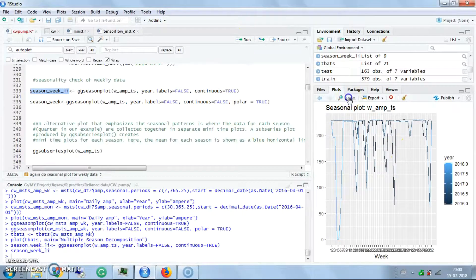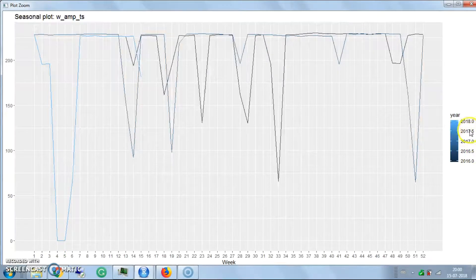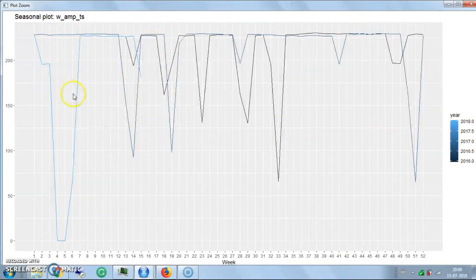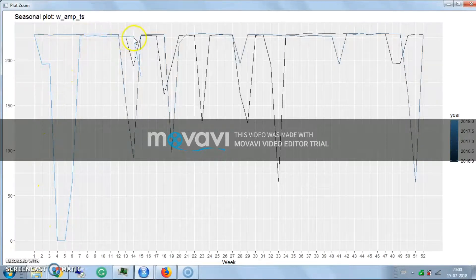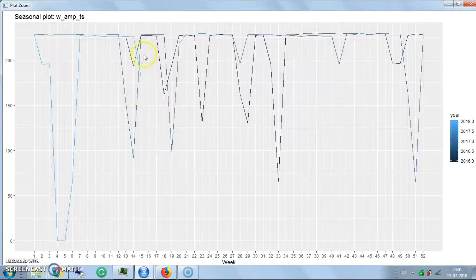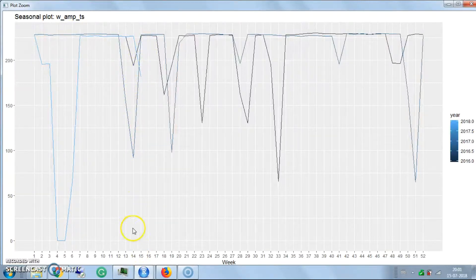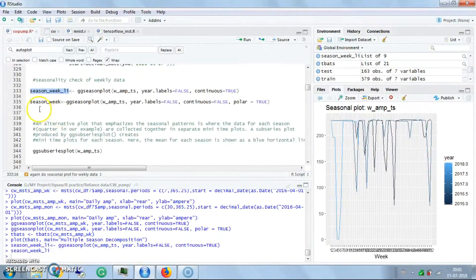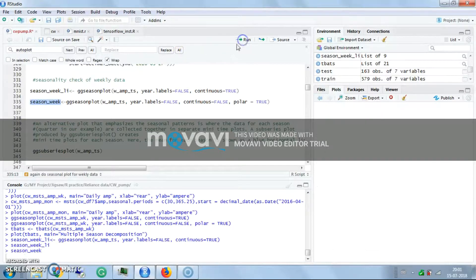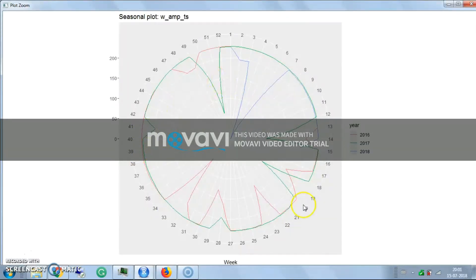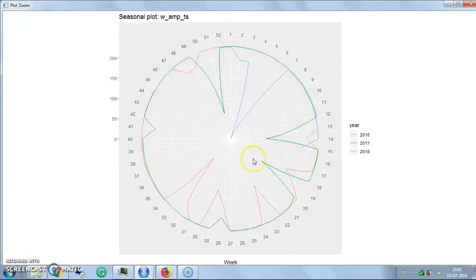This is for the week in periods 2016, 2017, 2018. You see in 2018 the pump initially remained stopped, but in 2017 and 2016 it runs differently - it stopped in the 14th week only. This type of information is given by the seasonal week plot. This shows throughout the year of 2016, 2017, 2018 how much the pump remains in stop conditions.